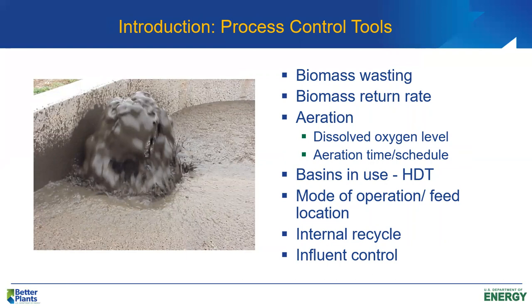Mode of operation is another process control tool. If we have a step feed activated sludge process, we can operate it in the step feed mode — distributing influent along the reactor length to smooth out the organic loading — or we can put all of the influent at the front and operate in the plug flow mode. We can also put all of the influent in the last compartment and operate in the contact stabilization mode. Controlling our recycle streams and how we direct influent through the plant is very important.